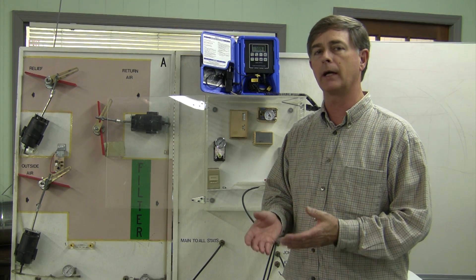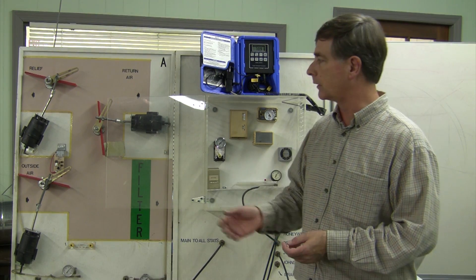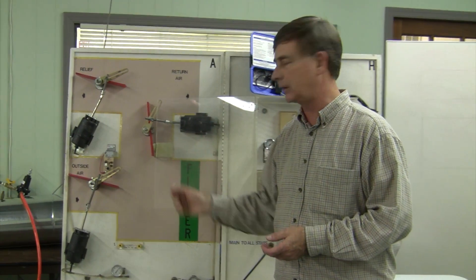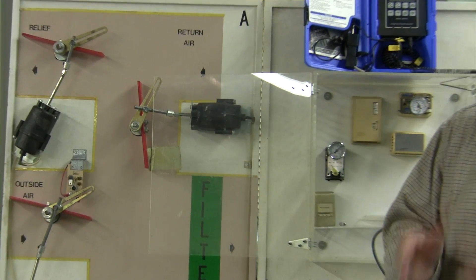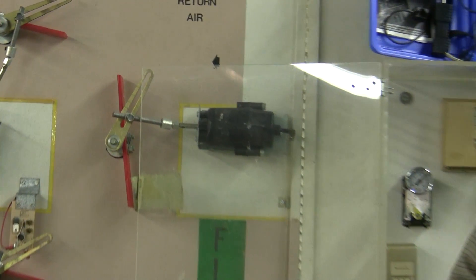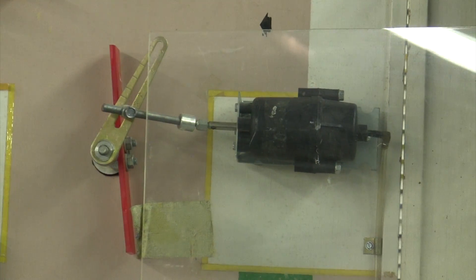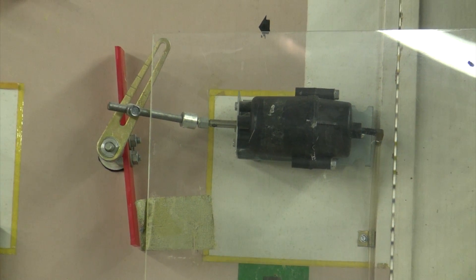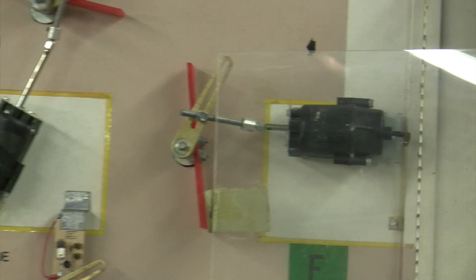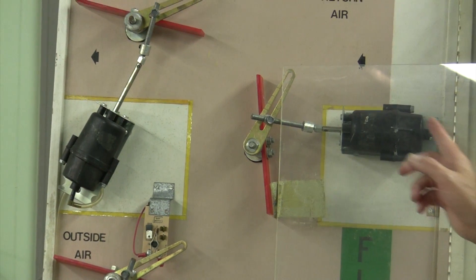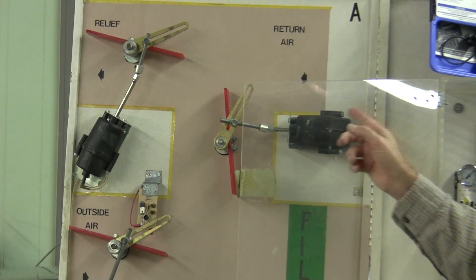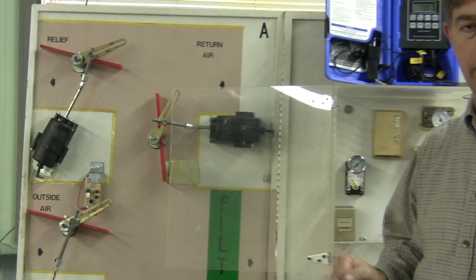We have to look at our actuator. If we look at an actuator that has a stroke of eight to thirteen PSI, then what we want to do is calibrate to mid-stroke of that actuator. So if you have a three to eight actuator, you're gonna have a very different calibration pressure. Check your actuator, find the spring range. In this case we have eight to thirteen.